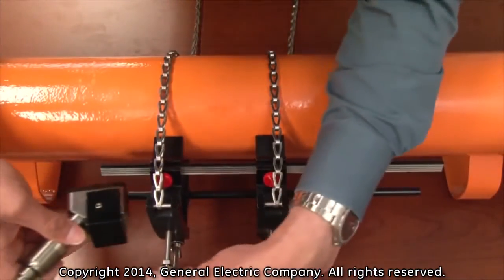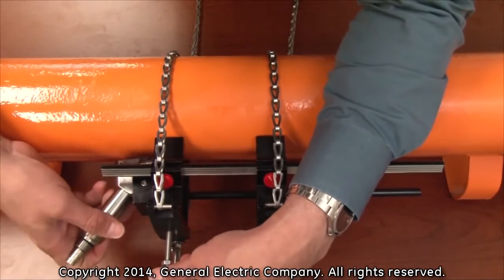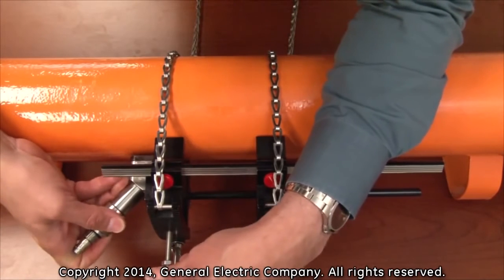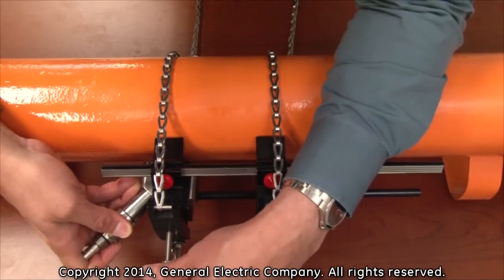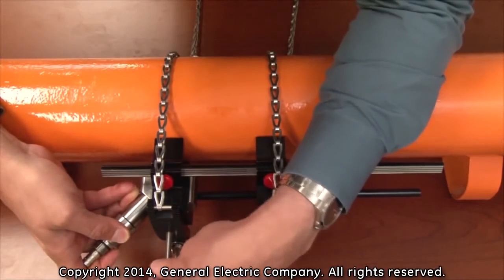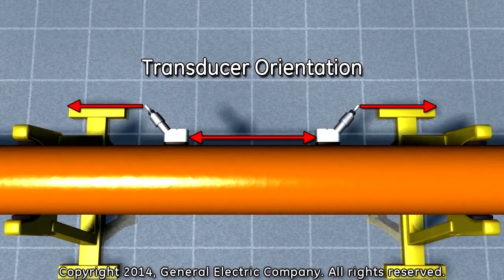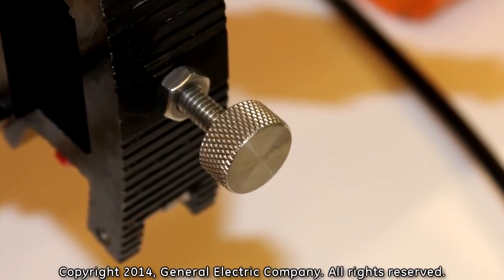For the installation, slide the transducer into the mounting fixture and ensure that the center bolt fits into the insert hole on the top of the transducer securing bracket. Make sure to orient each transducer toward each other so that the BNC connections on the other end of the transducers are facing outward. Tighten the transducer securing bolt on the fixture by hand.